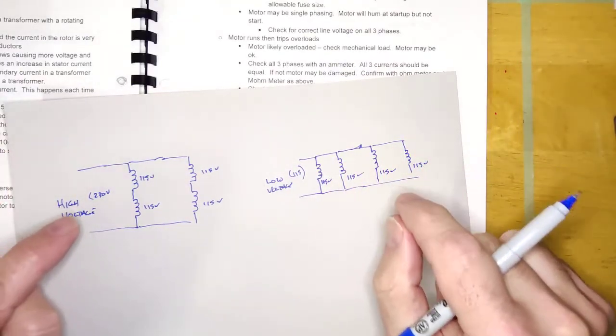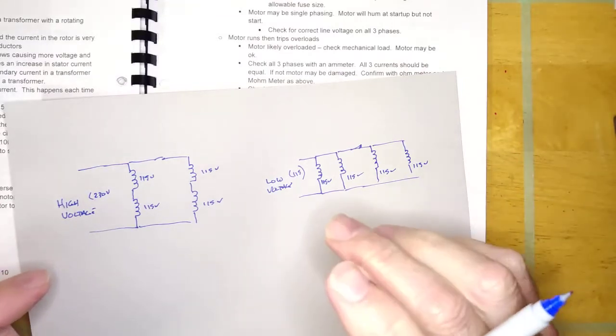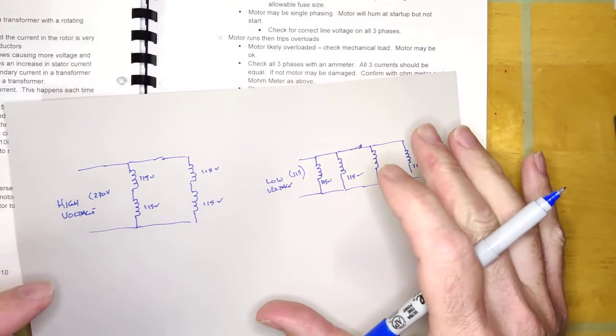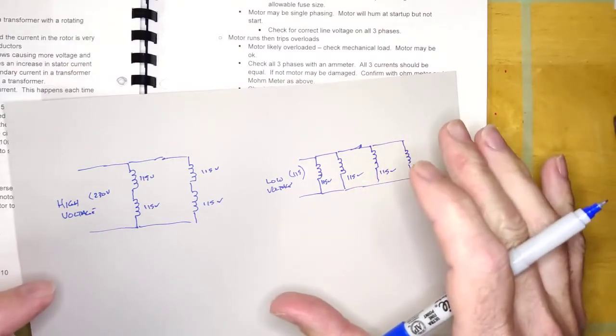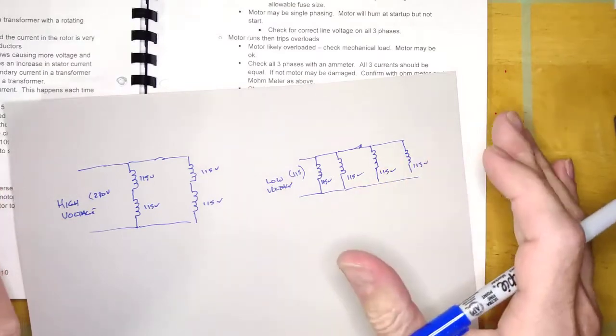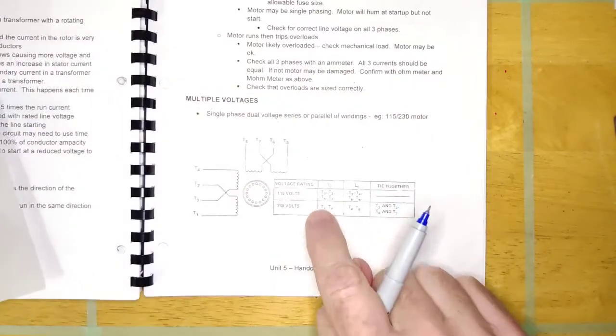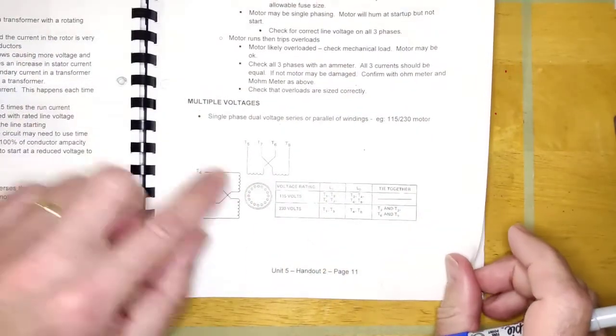And now you've just hooked it, everything in parallel, and so now it's connected low voltage. And that's because it's going to be, let's say, 115 for this particular machine here, which means this guy gets 115, this guy gets 115, this guy gets 115, and this guy gets 115.